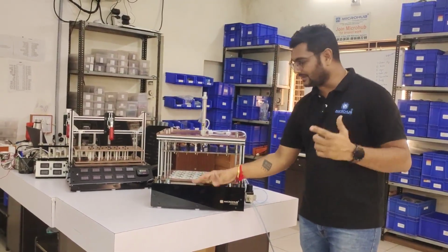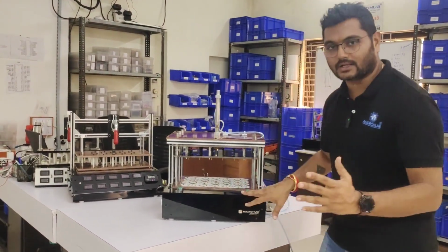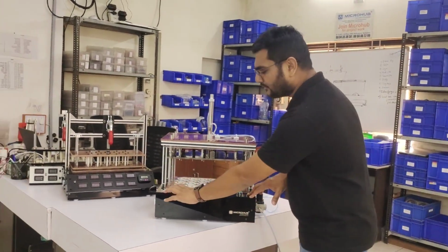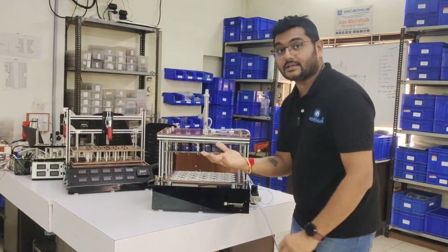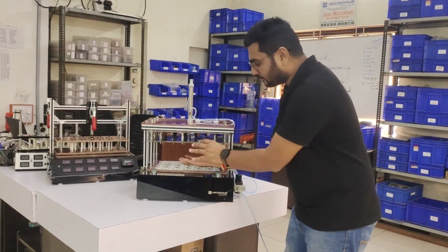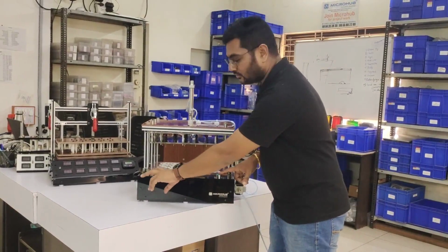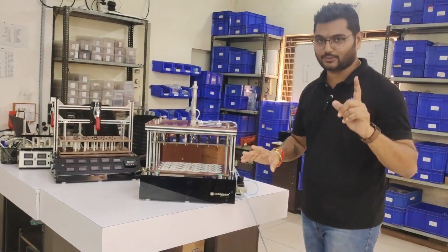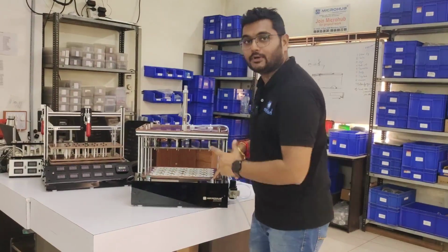Fifth, more important part, as I said, it will not give you a shock. Also, when the user is working on this test fixture, both hands should be on the test fixture, because if I am operating this test fixture with a single hand, there may be a chance the operator uses the second hand, and a particular pin may come onto the hand. So we have interlocked it with two push buttons. When I am pushing this and I am not pushing this other push button, it will not operate. Same if I am operating this push button and I am not operating the other push button, it will not work.